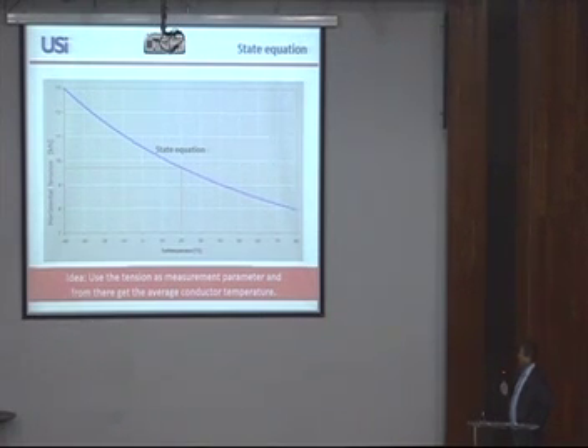That means we are ensuring with this measurement that we never violate clearance, which is public safety, and we never damage the conductor because we take care of a maximum temperature. So we would have a limit here and a limit tension which allows us to keep the conductor always at maximum 75 degrees in that case.